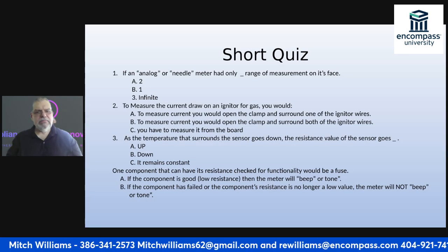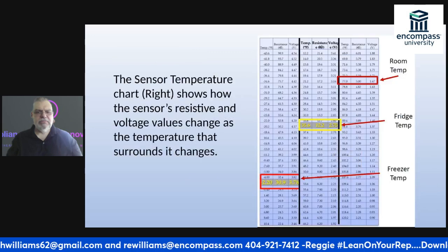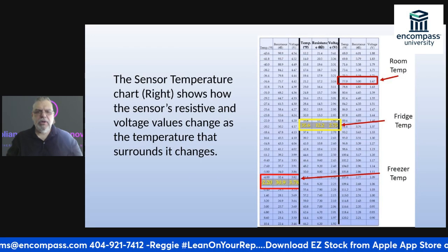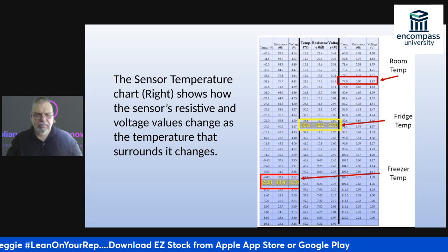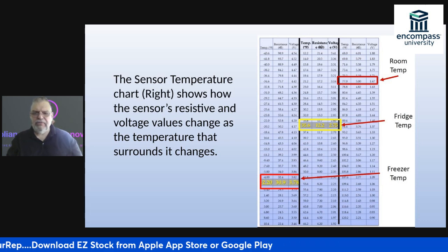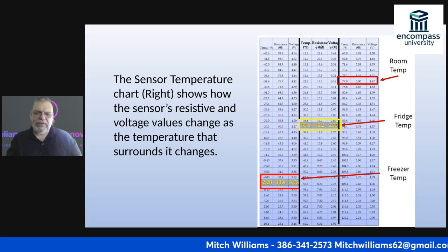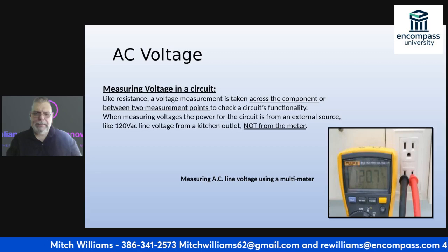Okay. Once again, I'm going to do it one more time. Somebody give me an answer. If my temperature goes down, my resistance goes up. Look there, 35.6 degrees, the resistance is 12.2. If my temperature drops to 2.2, my resistance is now up to 30.9.